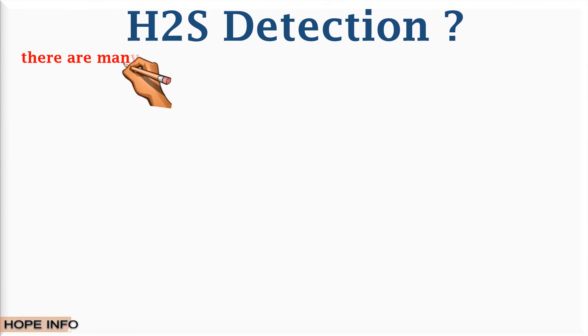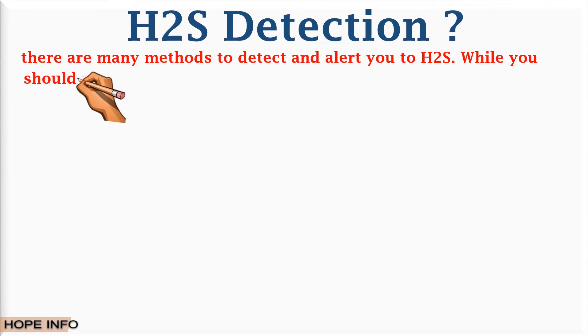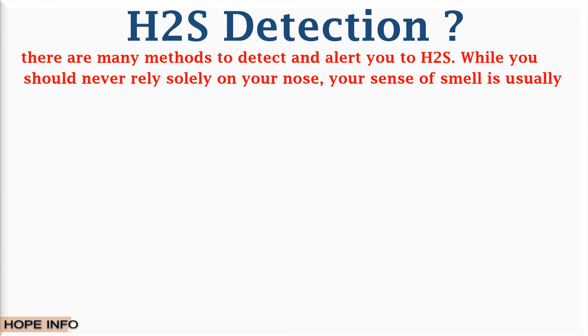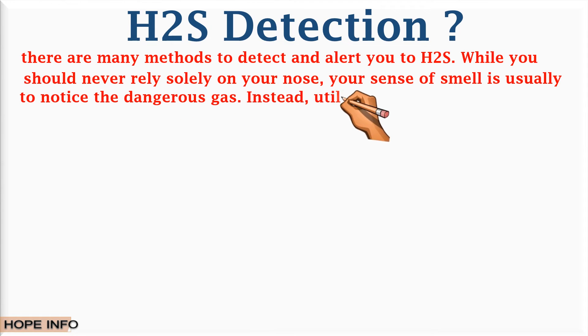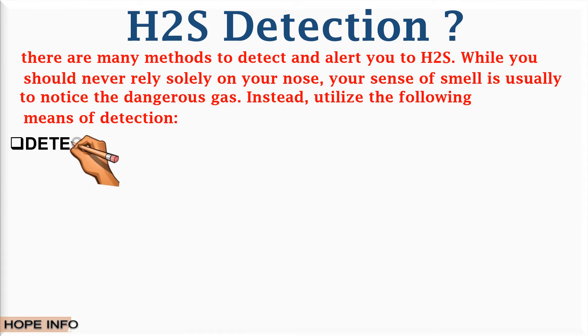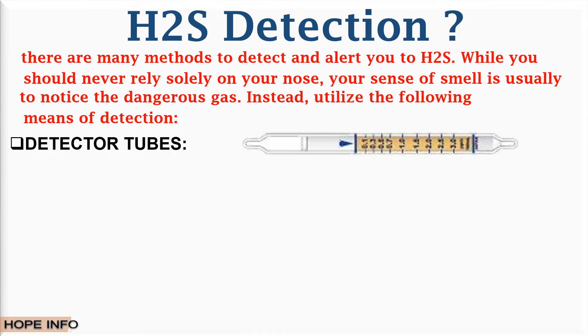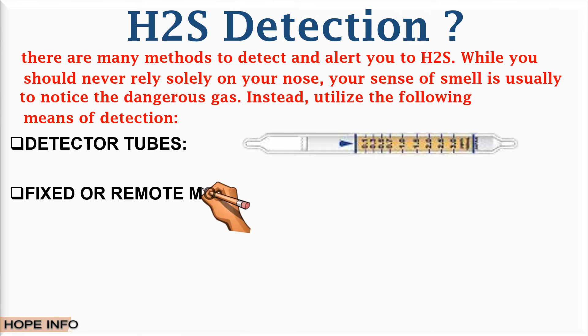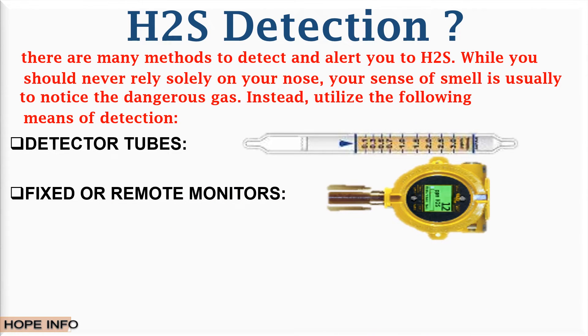H2S detection — there are many methods to detect and alert you to H2S. While you should never rely solely on your sense of smell, it is usually the first to notice the dangerous gas. Detection method number one is detector tubes: special tubes about the size of a pen that provide a measurement of H2S concentrations by changing color depending on the H2S level. Detection method number two is fixed or remote monitors: used in large sites for continuous monitoring, they trigger an alarm if H2S levels increase above safe limits, commonly set to alarm at 10 ppm.